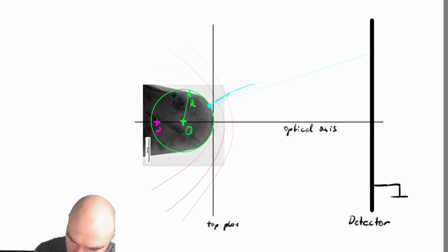On top of that, the detector, if you've got a straight flight path instrument, oh sorry, that was a sketch for ground, we're not going to ground yet. The detector is also, for technical reasons, probably going to be at some potential of 2 to 3 kilovolts negatively.